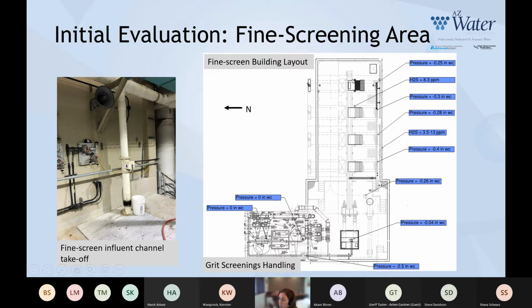A belt conveyor moves screenings from these fine screens over to the screening hopper, which are then discharged down into the truck loadout bay. We also found that foul air draft was insufficient to maintain negative pressures in channels throughout the fine screening room. Fugitive emissions through equipment and cover leaks was evident from elevated H2S concentrations in the room. But also, when I get to the photos of the smoke testing, you'll see this even more apparent.